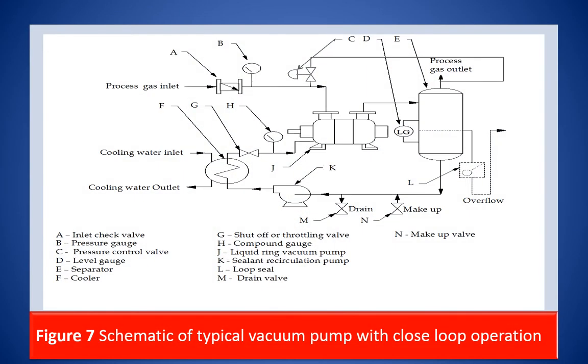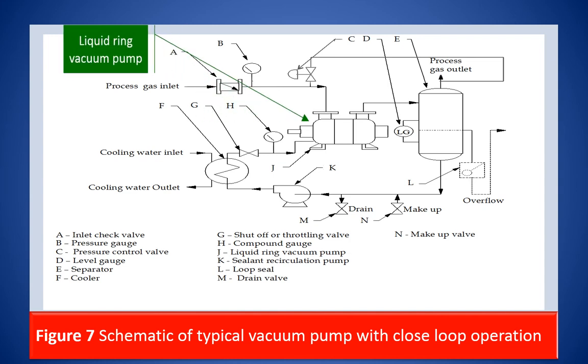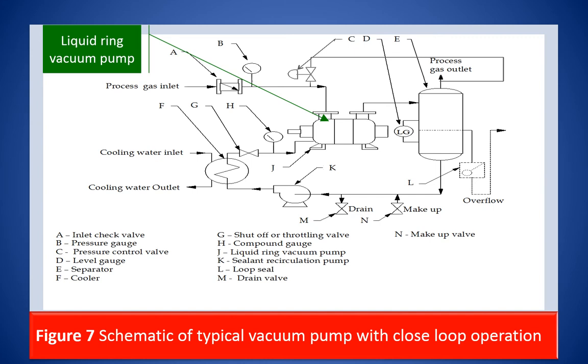Unlike other rotary pumps, the liquid ring pump is not a standalone pump — it is a package. The gas-liquid mixture discharged from the vacuum pump flows to a separator. From the separator, the liquid can be sent out to ETP or reused as service liquid. Usually the liquid is recycled back due to cost. Depending upon the vacuum required, the service liquid will vary, as will its cost. Due to gas compression there is a rise in temperature; hence, if the liquid is to be recirculated, it must be cooled before recycling.